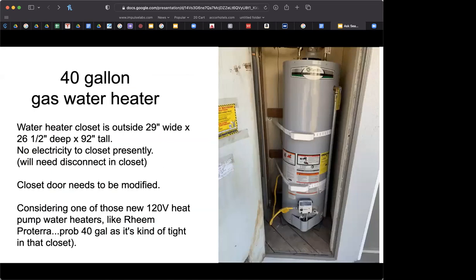It's a 40-gallon gas-fired water heater in a small closet. The way to put a heat pump water heater in there, you see the door is open on the left, is to cut out a much bigger part of the door to make a louvered or screened air-breathing doorway, letting the cold air out of the closet.